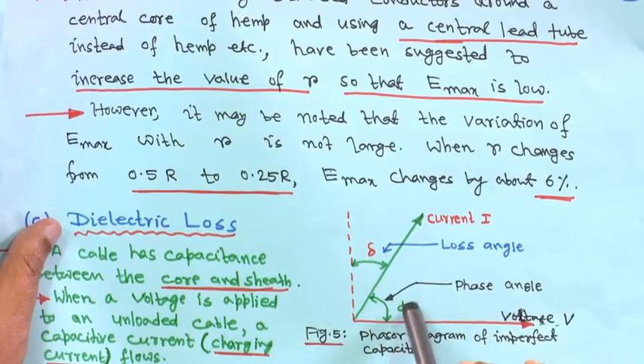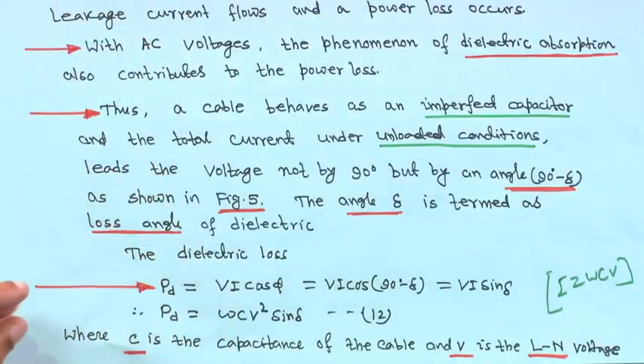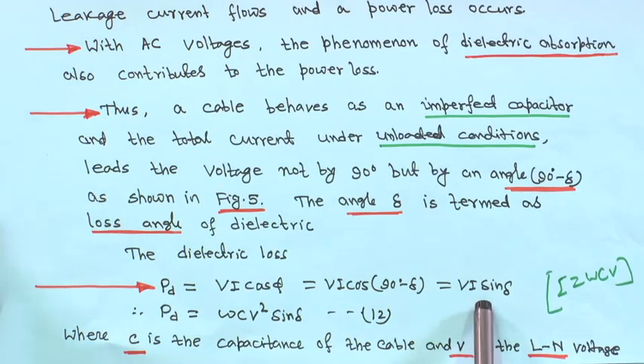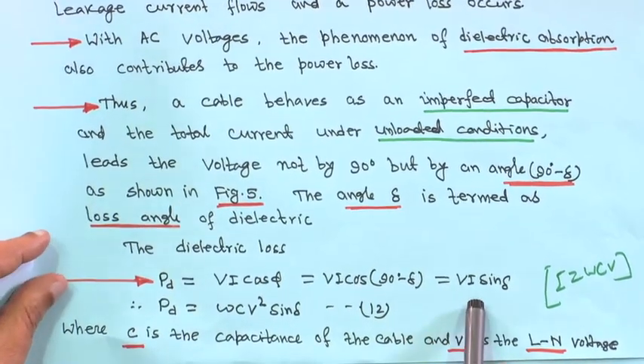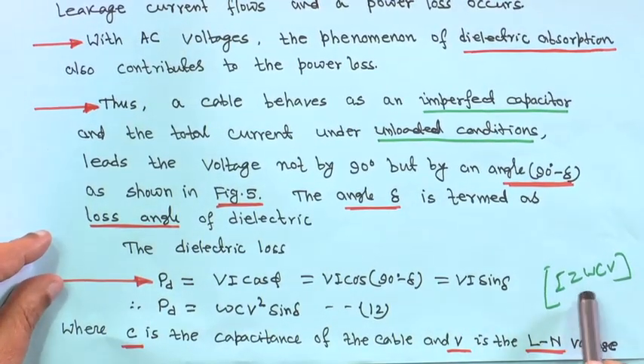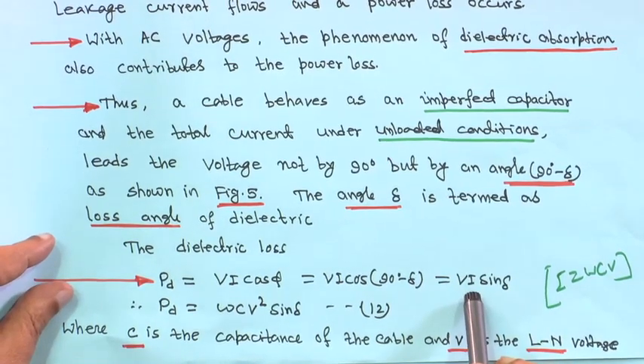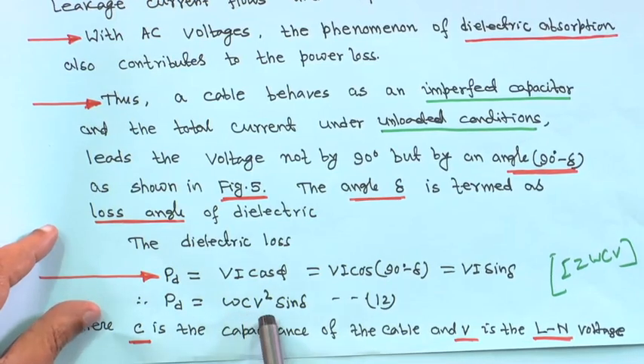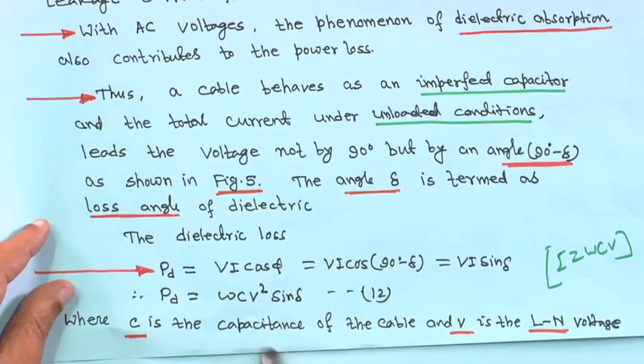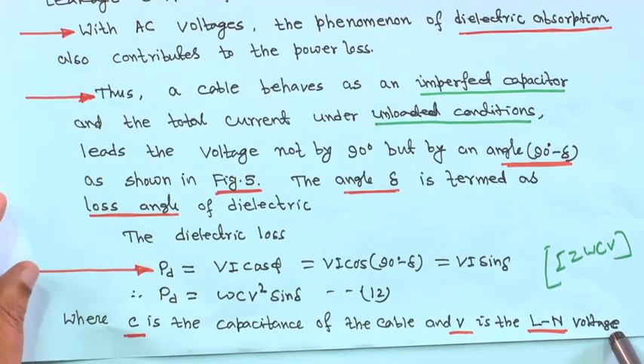Since φ equals 90 degrees minus delta, the power loss will be V·i·sin δ. We know i equals ω·C·V, so substituting, the dielectric loss will be ω·C·V²·sin δ, where C is the capacitance of the cable and V is the line-to-neutral voltage.